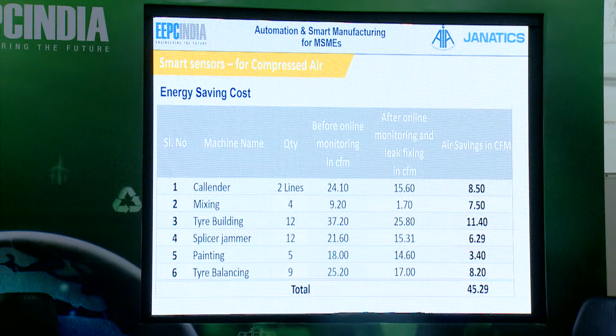There are a number of machines lined up, 1 to 6, showing actual air consumption and after online monitoring. Initially this was not implemented because you can't predict where each line leaks. Using the flow meter and energy saving method, we were able to identify the leakages, which was directly related to air savings in terms of CFM. It was supposed to consume a certain amount, but the actual saving is 45 CFM.